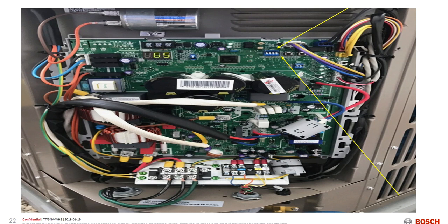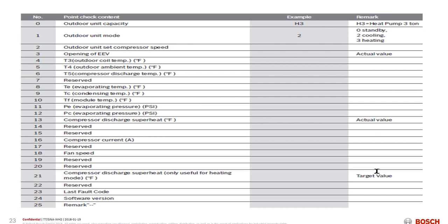The buttons on the right hand side, the force button on the right and the check button on the left, allow me to take this page, look at the left hand side of this page, and push that check button. I can record, I can see, I can diagnose what's going on inside the system, just like a doctor would do with an x-ray. I can push the button 8 times and see the evaporator temperature. Push the button 16 times and see the compressor amp draw. Push the button 23 times and see the last fault code.